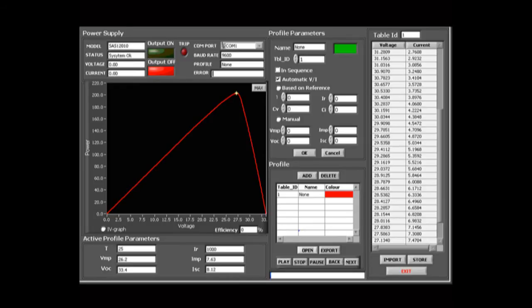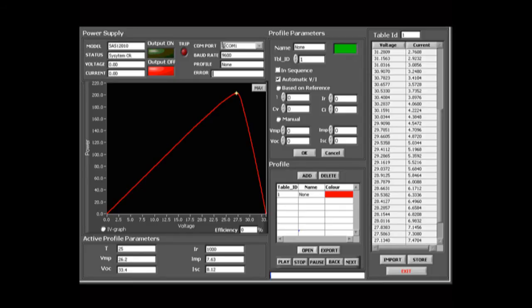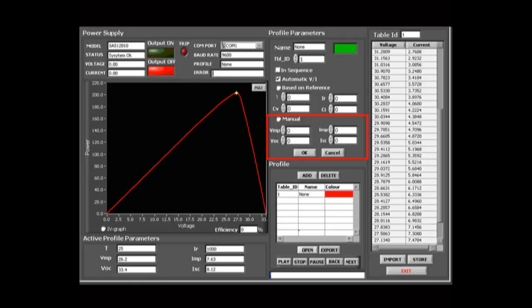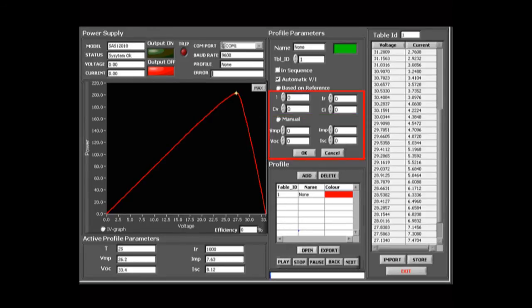The profile on the SAS 12010 is actually comprised of 50 points on a curve. The SAS 12010 performs linear approximation between the points. There are three ways to generate a profile curve. The first is to create a solar profile based on the four user-defined points: open circuit voltage, short circuit current, maximum power voltage and maximum power current with standard temperature and irradiance values of 25 degrees centigrade and 1000 watt per meter square.